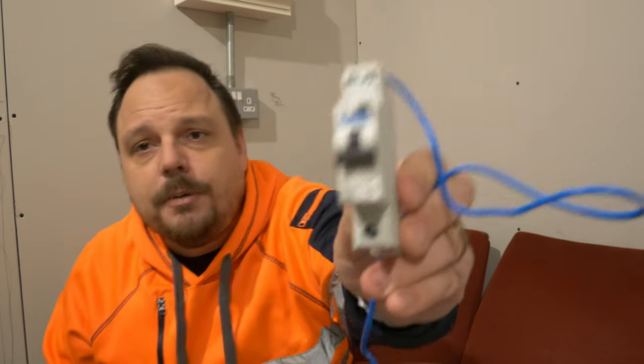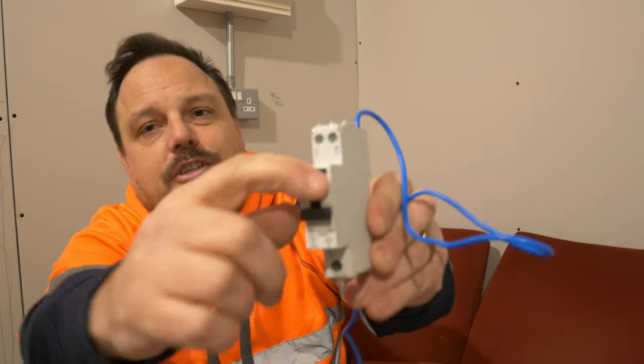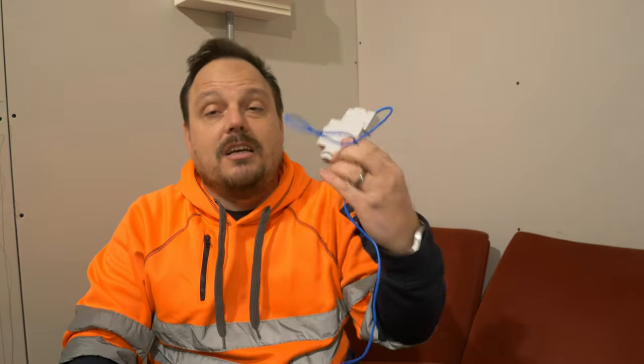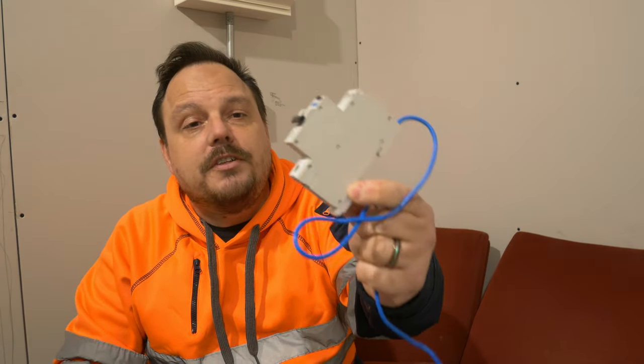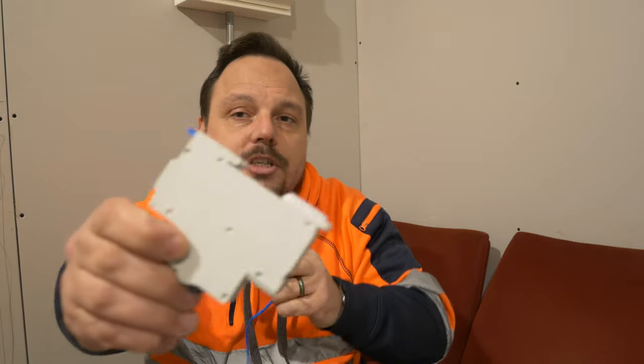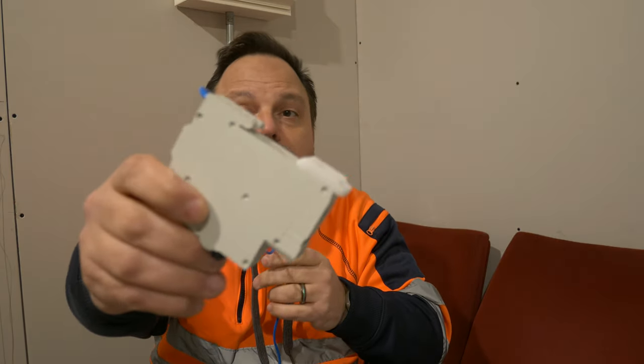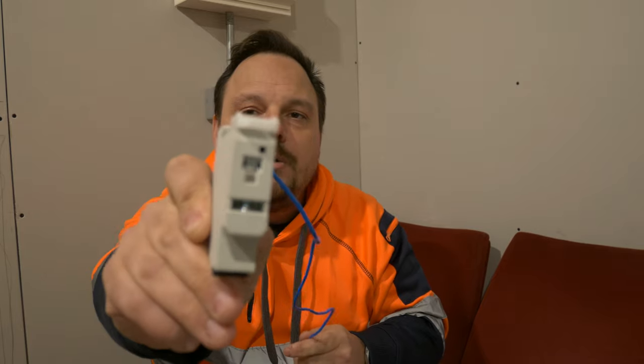It's got the test button on the top. So again, you've got a traditional RCBO for those of you who use these. And main point is, it's compact, fits in nicely, you've got your line and neutral in the top. I like the way it mounts onto the busbar so you know if it's in there or not. It does still have the traditional method of hooking onto a DIN rail that a lot of other overcurrent protected devices do, and you have got the cage clamp on the bottom still, so if you want to connect this onto a busbar in a different enclosure or a different product that happens to have a different connecting mechanism, then you can still do that.